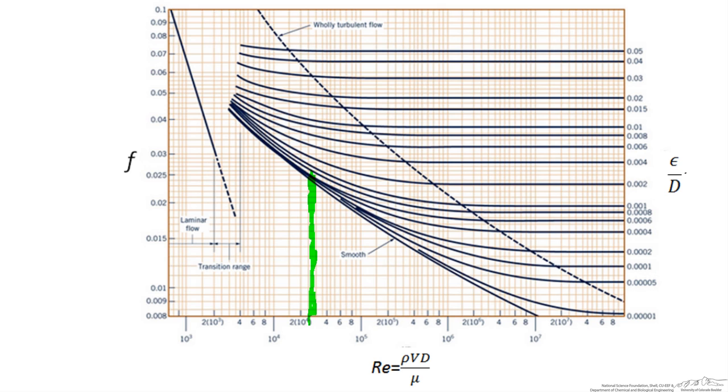So our roughness factor for our copper pipe can be looked up in a table and found to be 5 times 10 to the minus 6 feet. Our diameter we already converted into feet as 0.0833 feet. This gives us a relative roughness factor of 6 times 10 to the minus 5, which falls right above this line of 5 times 10 to the minus 5. So if we follow those up until they intersect we get a frictional factor of about 0.024.